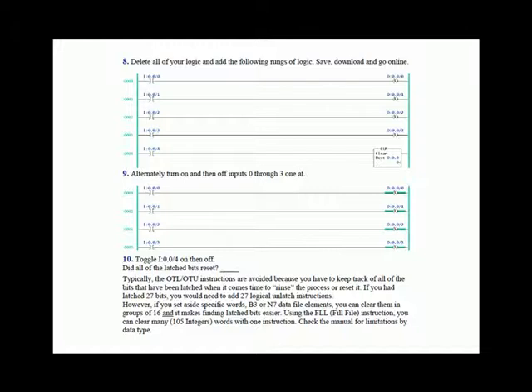We then had you toggle input 4 on and off. Did all of the latch bits reset? Yes, they did. This demonstrates that programmers typically avoid the latch and unlatch instructions because they don't want to keep track of all the bits they've latched when it comes time to reset the process. If you latch all the way through your program, you have to go back and unlatch. If you had latched 27 bits, you would need 27 logical unlatch instructions.